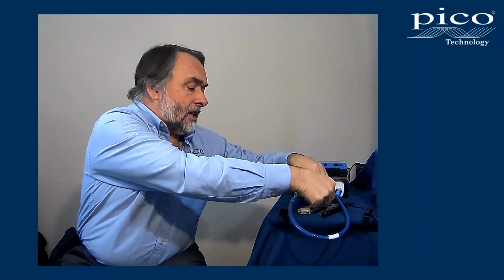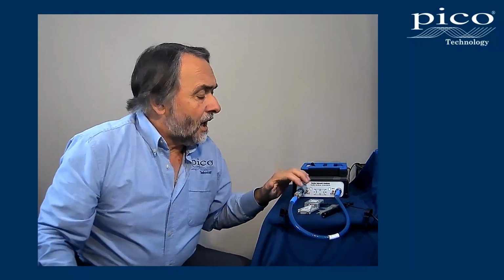And we can also make a fairly good load. And obviously that adapter, precision made, can be a very good through. So we're very happy that when we calibrate with these, we've got very highly reflective ports, very well matched port, and a very good through, very well matched as well. Now, an eCal module is slightly less good. An eCal module has these switches internally, and the switches will add inductance, capacitance, impedance in series with the hard short, the good quality open and the good quality load. So these are not quite so ideal in terms of calibrating the complete area of a Smith chart.